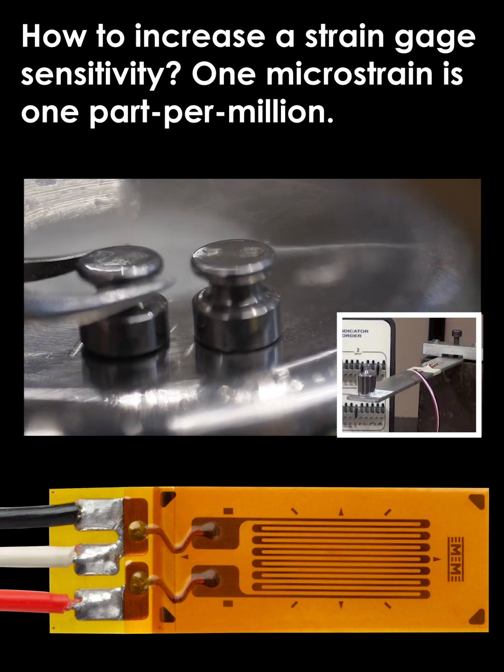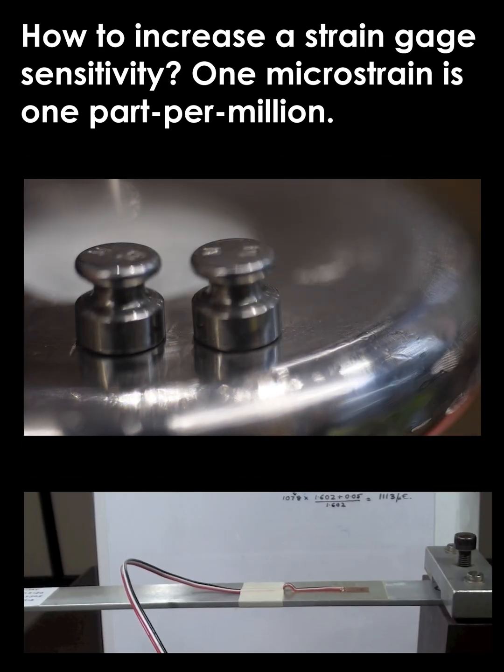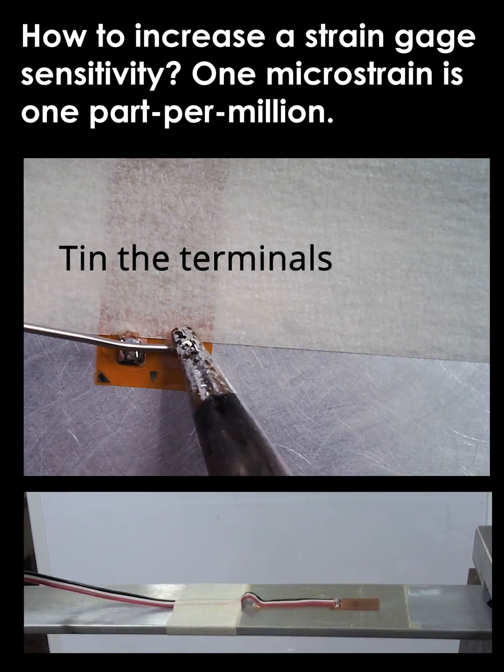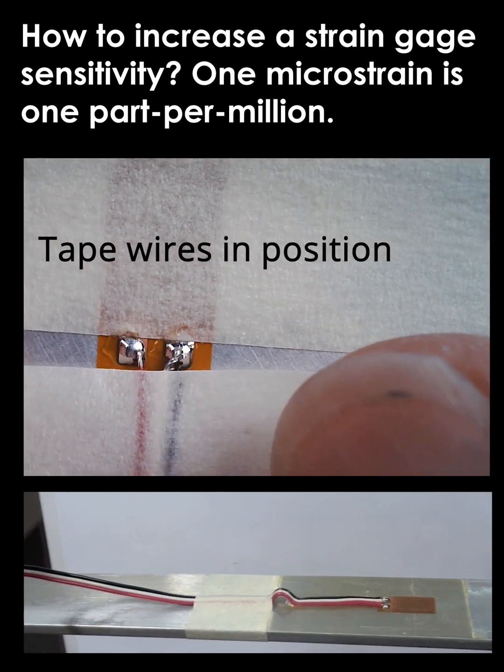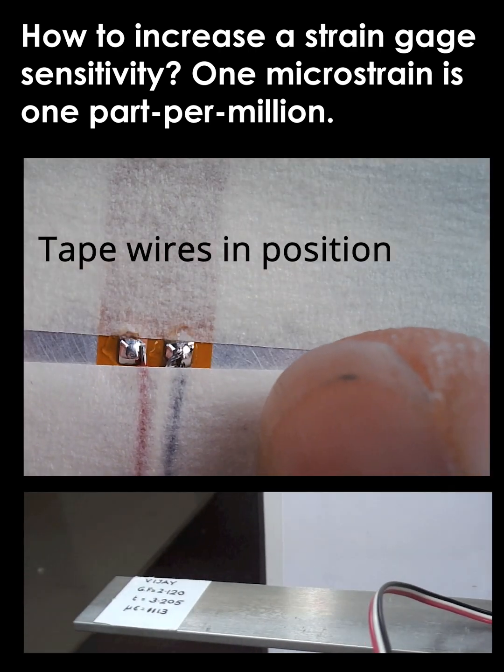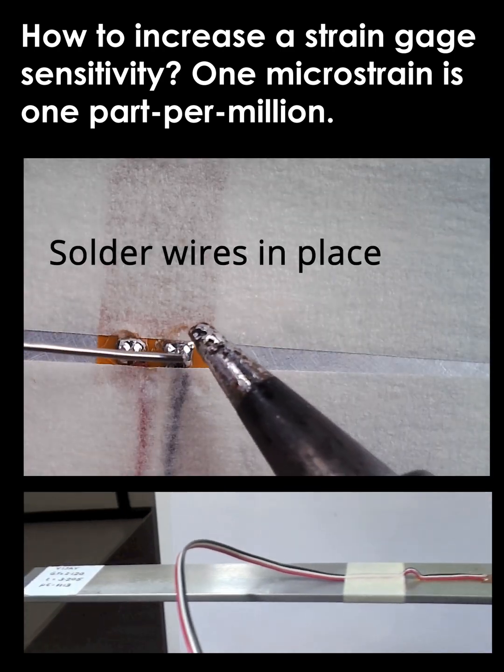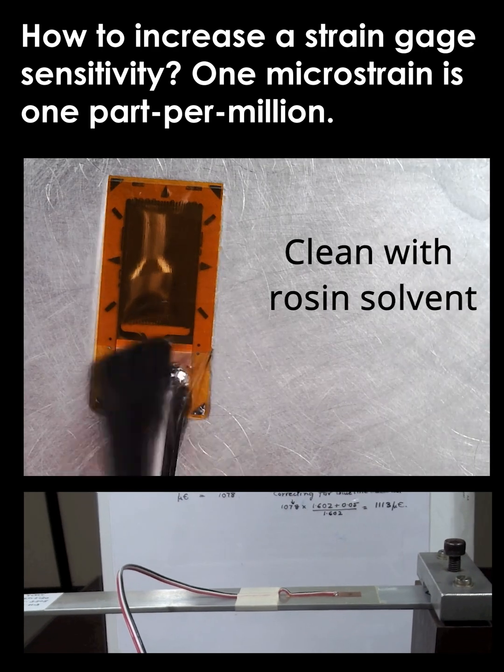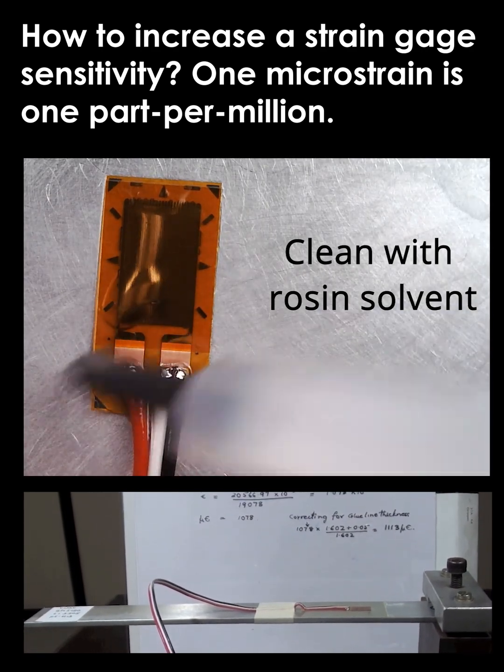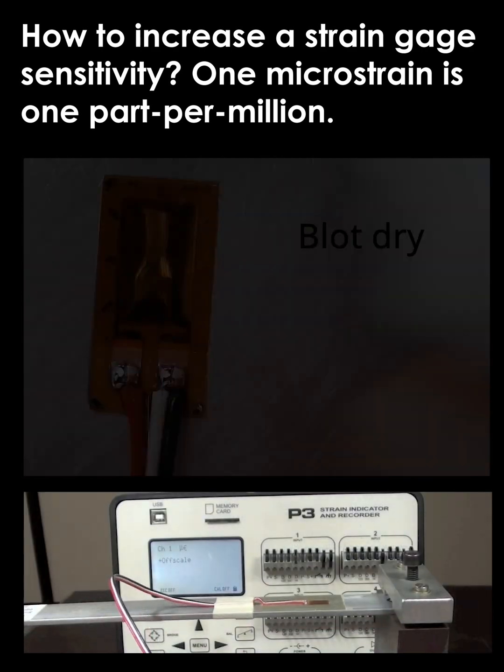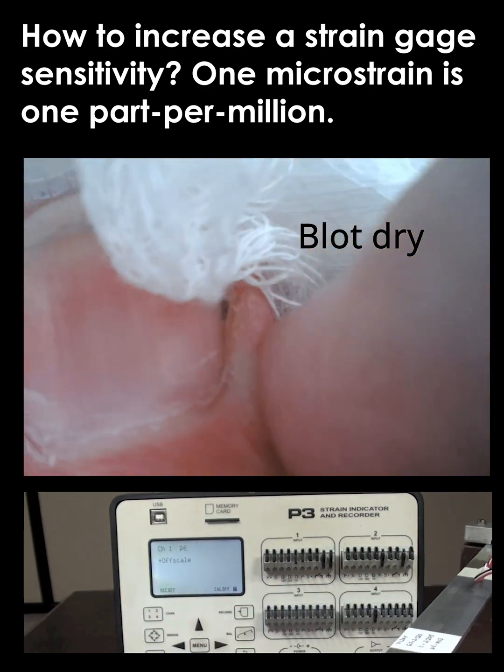This is an example to show the sensitivity of a strain gauge. Here we have an example with a CEA series strain gauge bonded onto it. When we go through the calculations, we find that the microstrain expected is 1113, and the strain gauge has a gauge factor of 2.120.